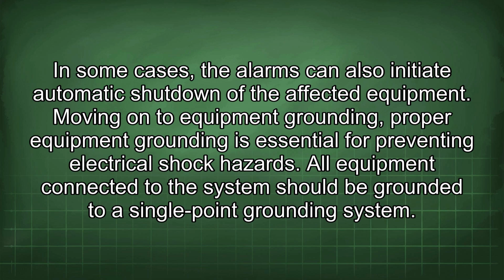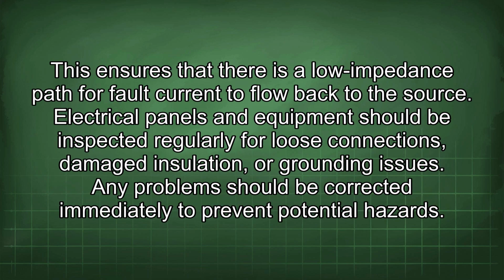Moving on to equipment grounding. Proper equipment grounding is essential for preventing electrical shock hazards. All equipment connected to the system should be grounded to a single-point grounding system. This ensures that there is a low impedance path for fault current to flow back to the source. Electrical panels and equipment should be inspected regularly for loose connections, damaged insulation, or grounding issues. Any problems should be corrected immediately to prevent potential hazards.